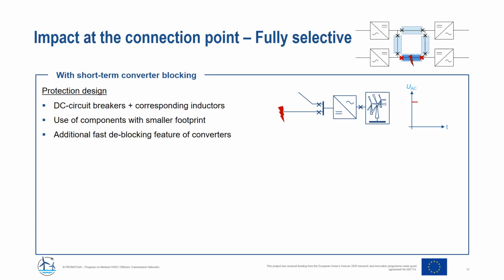Depending on the protection system design, a fully selective strategy might still lead to blocking of the converters during fault clearing, especially if, for example, breakers with longer fault clearing times or smaller inductors are used, which might be done for having a smaller footprint of the components, which is especially relevant for the offshore platforms. In that case, to have a fast resumption of the power flow after the line has been resumed, an additional fast deblocking feature of the converters is needed.